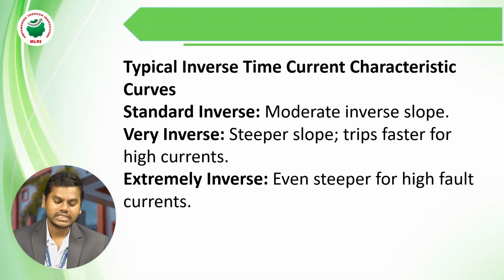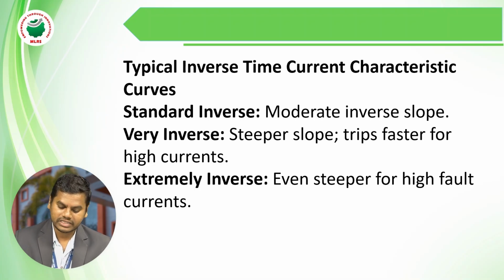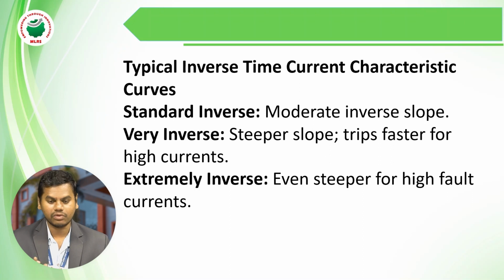First, standard inverse, where a moderate inverse slope is involved. Next, very inverse, which has a steeper slope and trips faster for higher currents. And last, extremely inverse, which is even steeper for high fault currents.